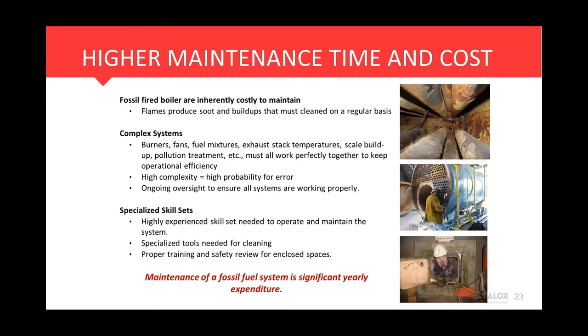All of that really gets factored in when you start looking at maintaining the system. This is a combustion process, so soot is formed, meaning someone has to get in there and clean on a regular basis. You have the burners, fans, oxygen fuel mixtures, treatment of the exhaust, and scale buildup inside the boiler itself to maintain. All of this means a more complex system, higher probability for error, more likelihood something goes wrong, and eventually one of those unplanned shutdowns, which factors in significant cost in lost production.